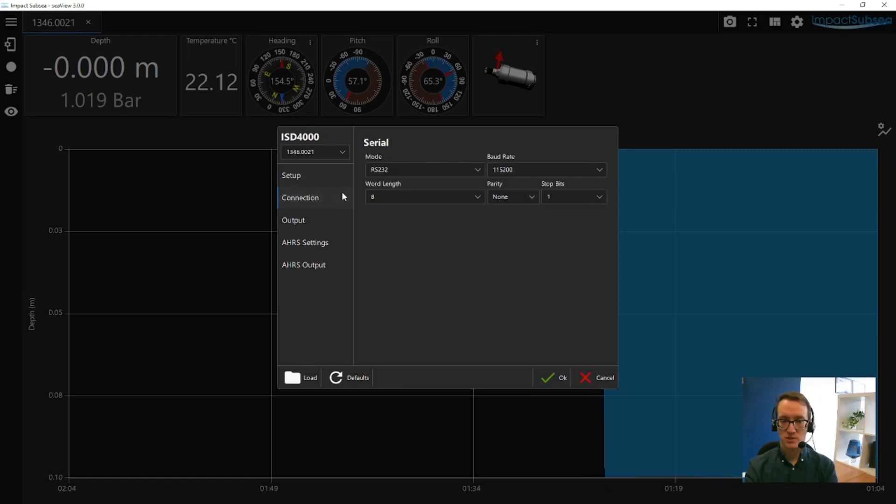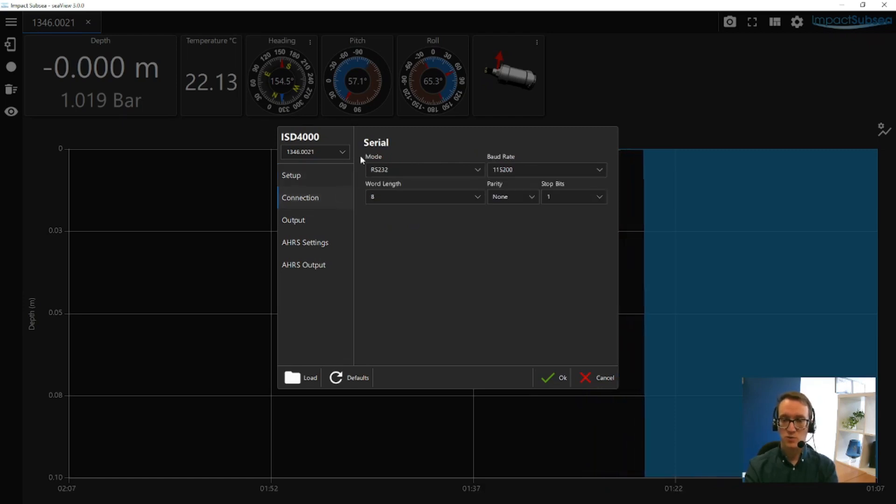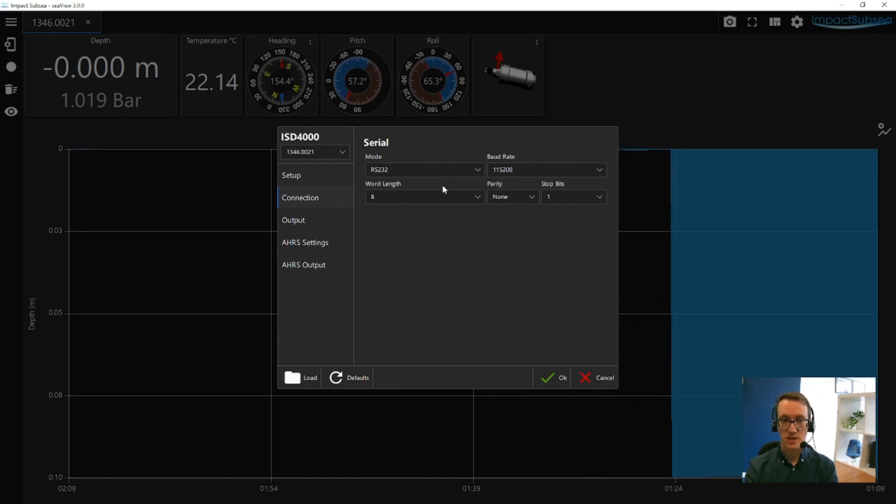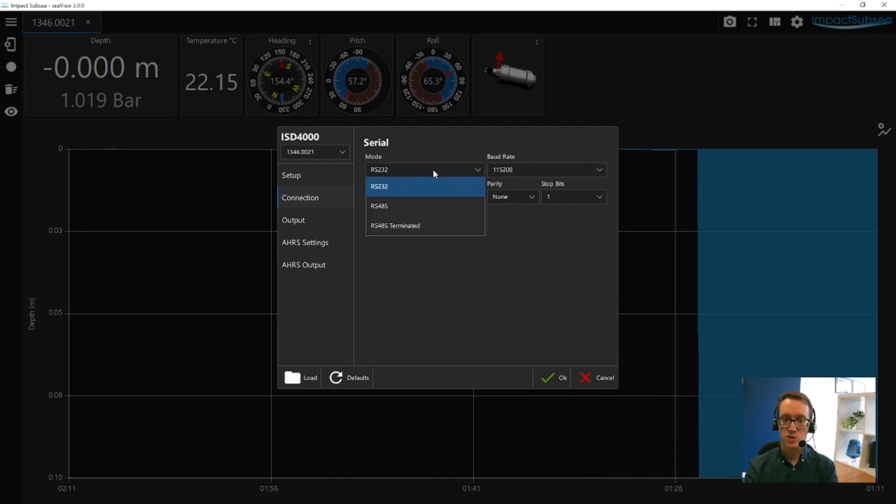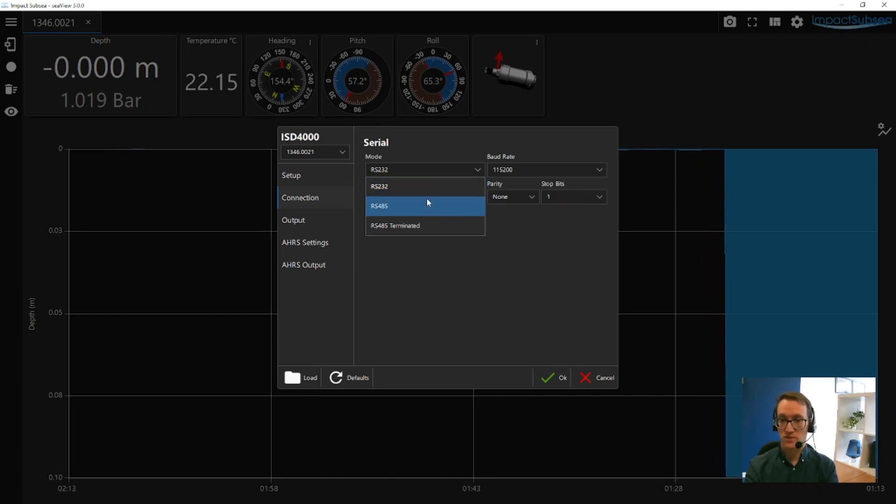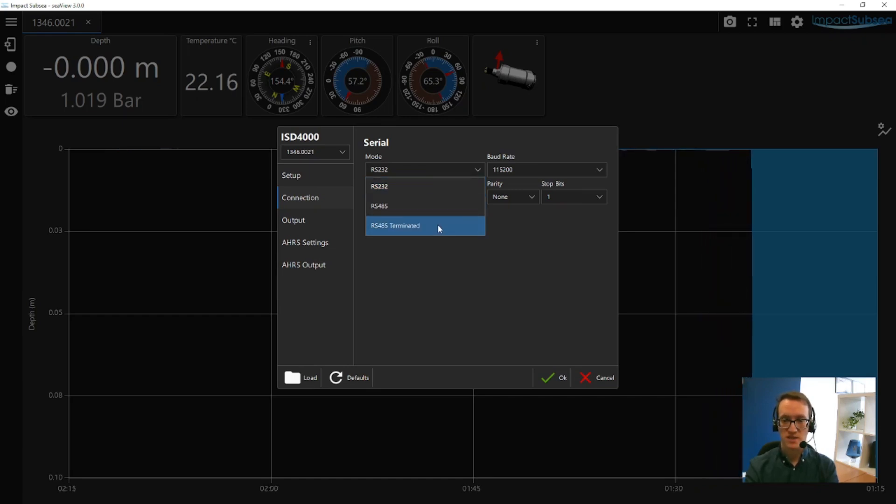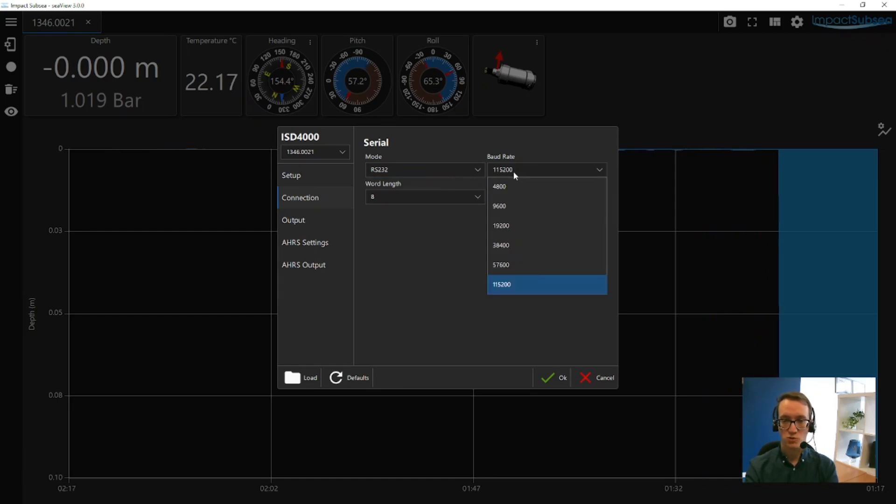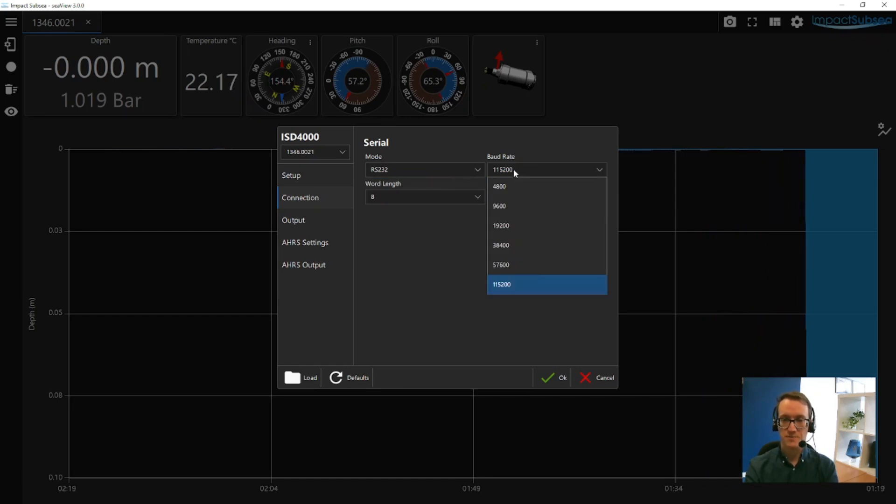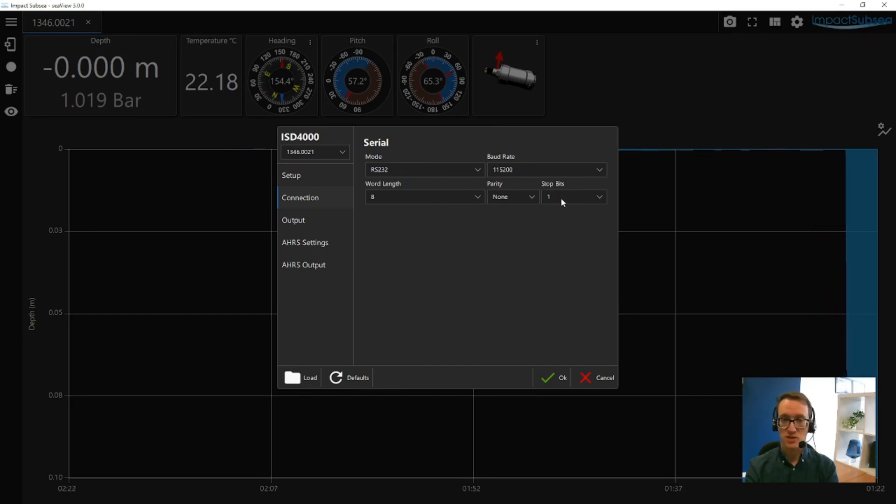The next settings window to go into is the connection window. Now from here, you can set the serial communications mode of the sensor, which can be RS-232, RS-485, or RS-485 terminated. And you can also set the baud rate required on the sensor, together with the word length, parity, and number of stop bits.